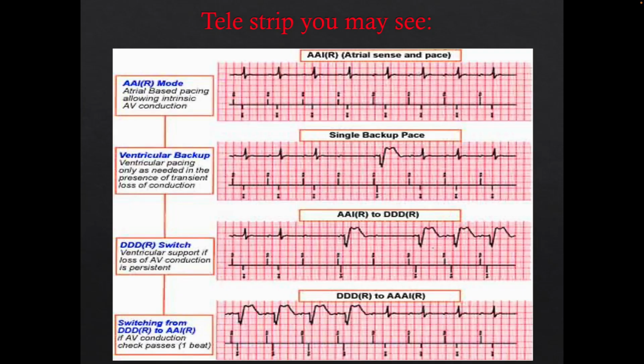So this starts as an AAI mode. It's A-sense and V-sensing. Then in A-senses, there's no ventricular native or intrinsic response. That's why you don't see anything there. So then what it does, it AV paces. So now it goes from AAI to DDD. These devices do that because it's trying to allow intrinsic rhythm or native rhythm to reduce any kind of pacing. So if you saw this, you'd be like, oh God, the pacer's not working. Call Jen, Fran, or Shipra. What's happening here? But this could be a natural phenomenon from the device because of how it's set.